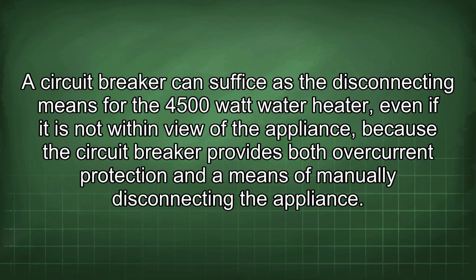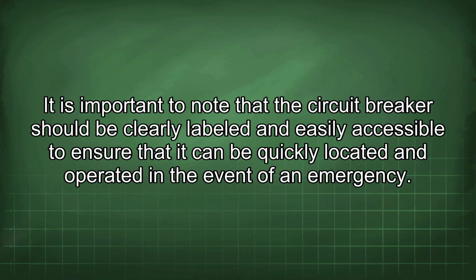A circuit breaker can suffice as the disconnecting means for the 4,500 watt water heater, even if it is not within view of the appliance, because the circuit breaker provides both overcurrent protection and a means of manually disconnecting the appliance. It is important to note that the circuit breaker should be clearly labeled and easily accessible to ensure that it can be quickly located and operated in the event of an emergency.